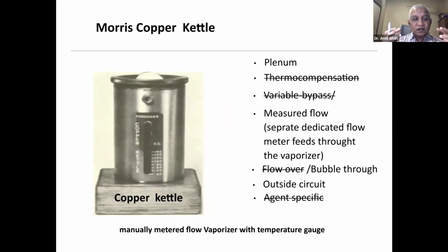So what anesthetists had to do was pass a special line, which was connected to this particular copper kettle. You pass 1 liter through this and 9 liters straight away directly outside the vaporizer, and then both of them are mixed in the end. So you have to separately calculate the flow which you need to pass through the vaporizer.